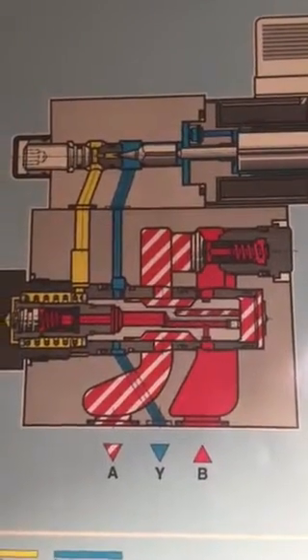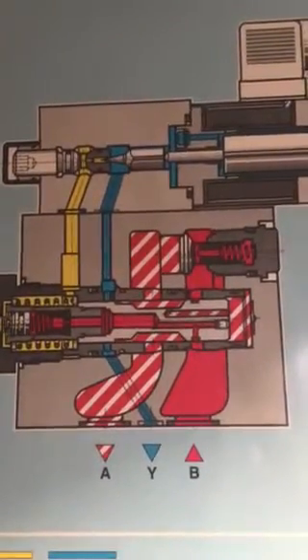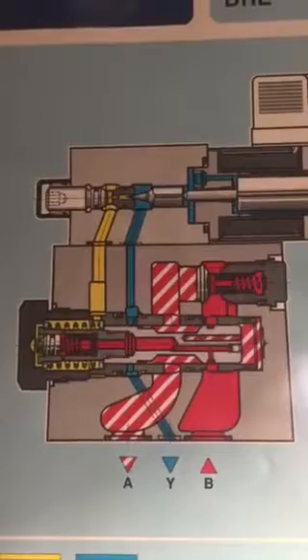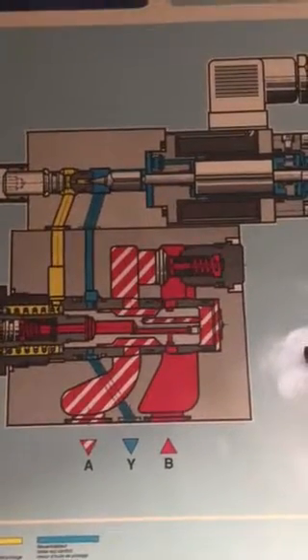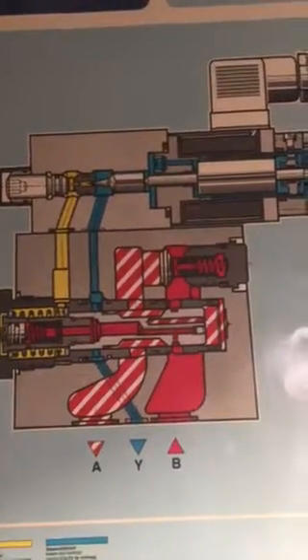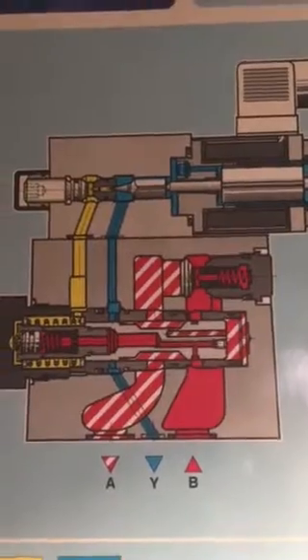So this is the proportional pressure reducing valve. You need to understand the proper function of this pressure reducing valve — how it operates and how the different pressures help control the pressure at some section of the machine. It is all electronically controlled. If we want to reduce the pressure at different times during the machine's function, we can do so with an electronic signal to this part of the proportional pressure reducing valve, enabling different applications in different plants and machinery.